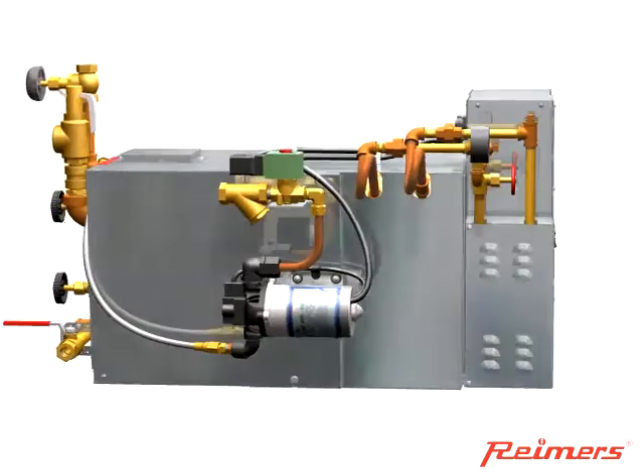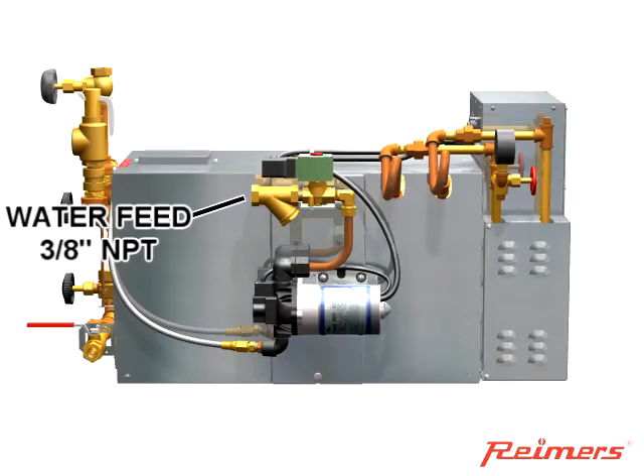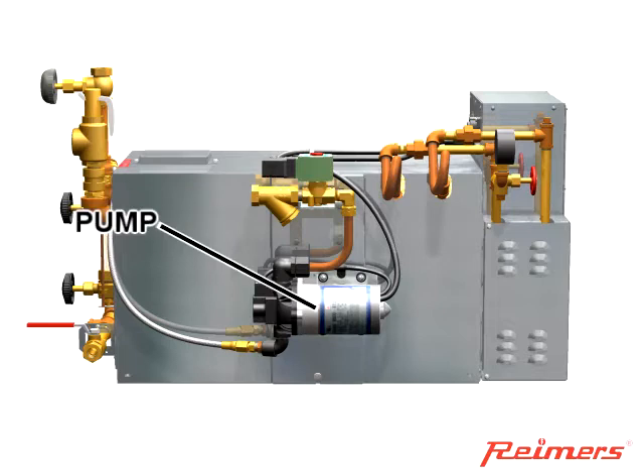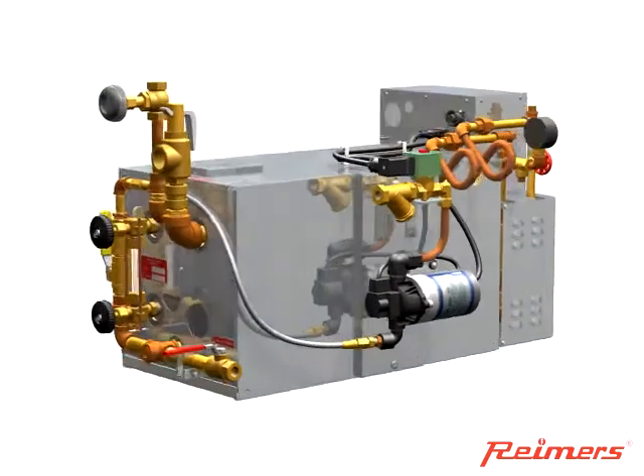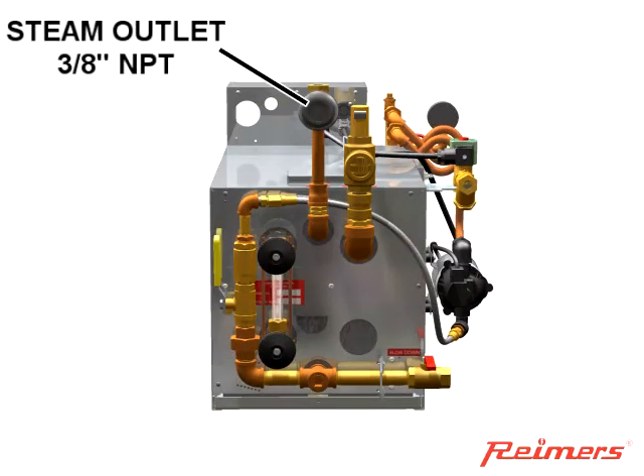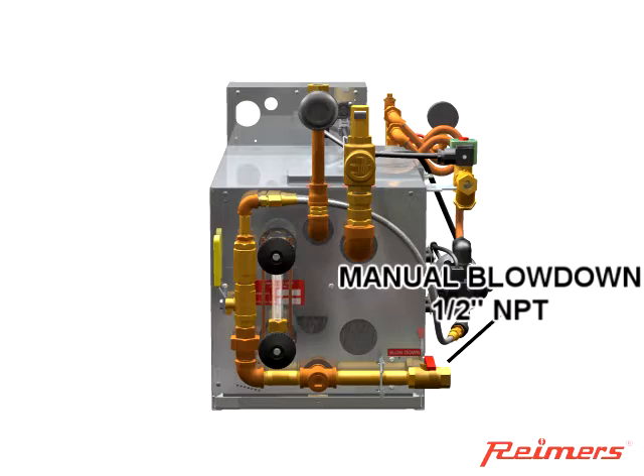A 3/8-inch feed water connection is provided. The boiler includes a solenoid valve for water feed control, and if ordered, a pump will increase the feed water pressure so that it can properly overcome the steam pressure within the boiler. Steam discharge from the boiler is controlled by a 3/8-inch globe valve that can be adjusted for proper flow.